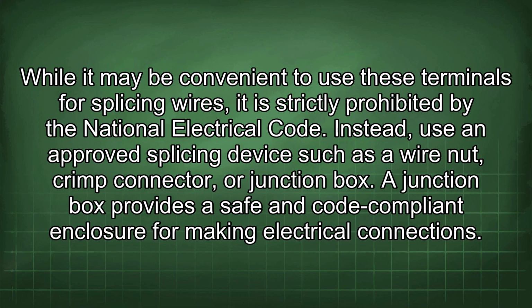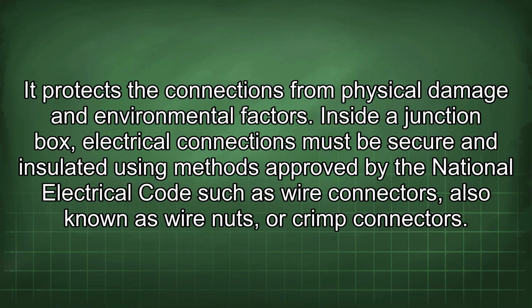While it may be convenient to use these terminals for splicing wires, it is strictly prohibited by the National Electrical Code. Instead, use an approved splicing device such as a wire nut, crimp connector, or junction box. A junction box provides a safe and code-compliant enclosure for making electrical connections. It protects the connections from physical damage and environmental factors.